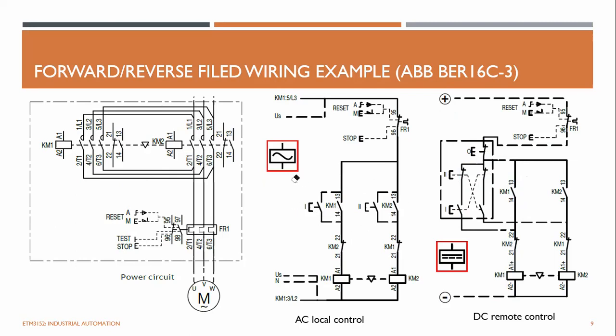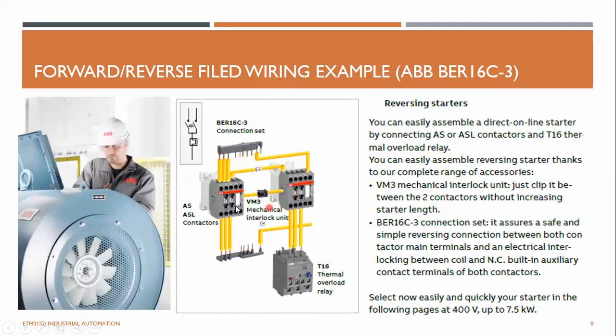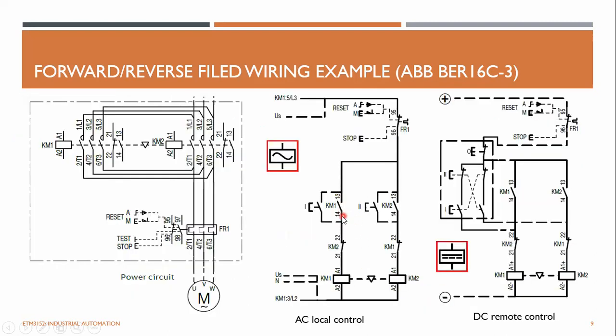If you have this circuit breaker, you have to see these numbers correctly. And when you're wiring, like 14, 13, which goes to where, and like that, to complete this wiring. I have just explained the logic, but when it goes to the field, if you want to replace any contactor that is damaged, you have to be careful and follow these numbers, and then it will be easy.